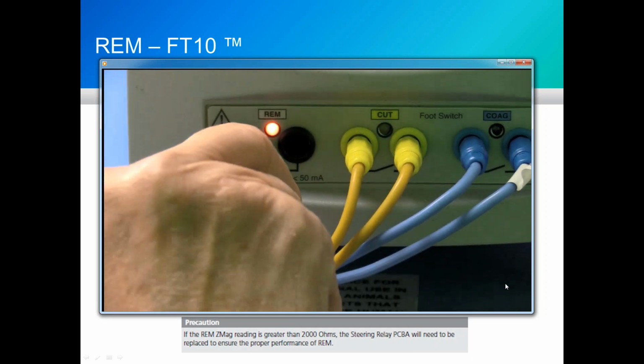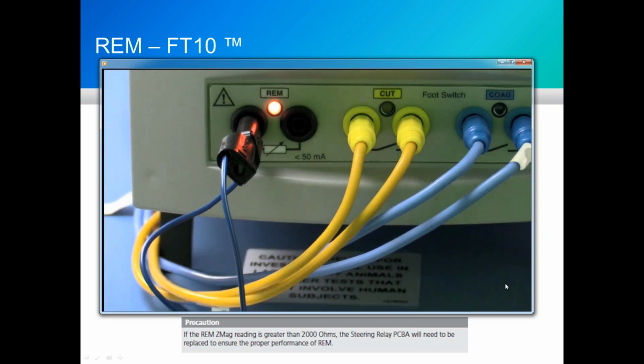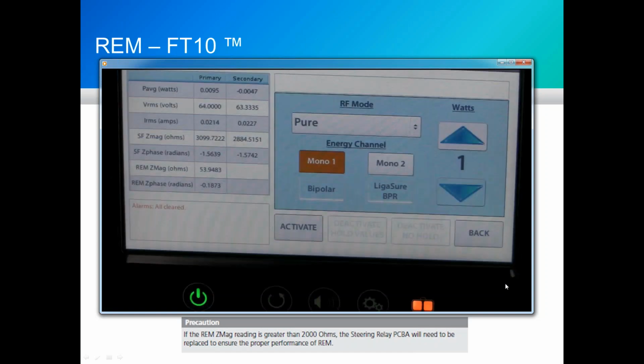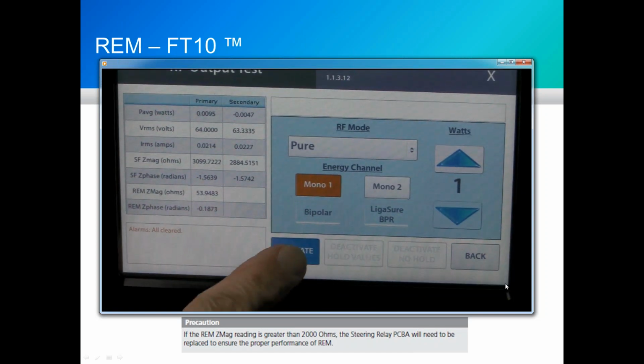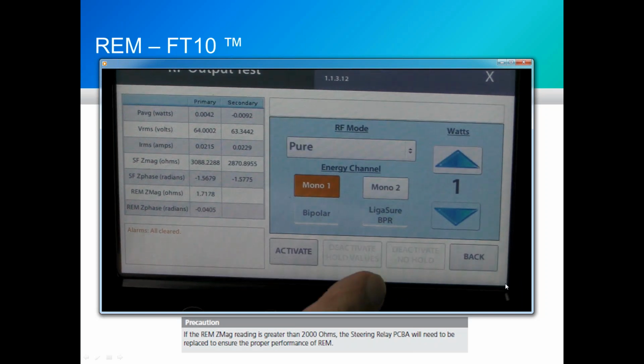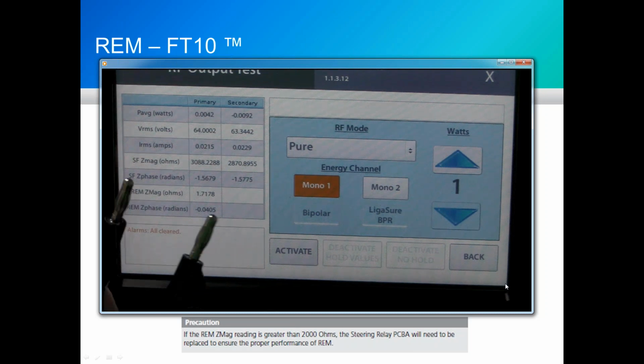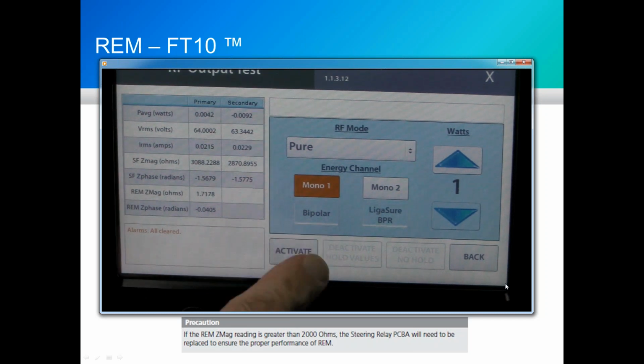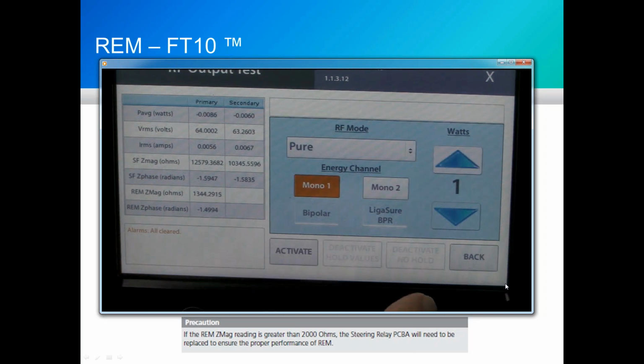I'm going to short the two connections together now for our 0 ohm. And you see we captured 1.7 ohms of resistance there. So in actuality, that REM cable that I'm using has some resistance associated to it as well, as you can see. Now for the last step, we are opening the circuit. We measure 1344 ohms. Our limit here is anything below 2000 ohms is acceptable, and our REM test is now complete.